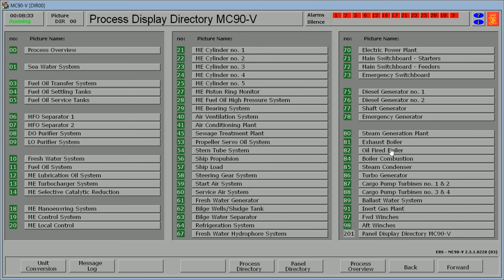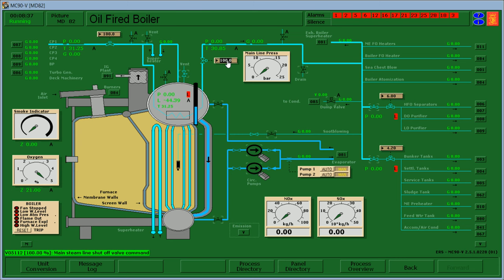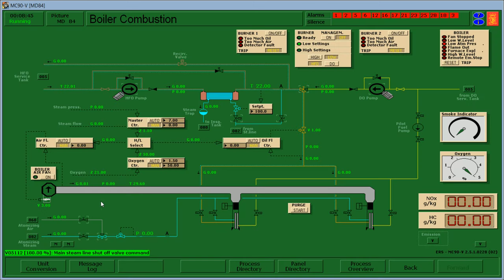Then proceed to the steam generation plant, oil fired boiler. We open the vent, close the steam line, then for the boiler combustion, open the atomizing air shutoff valve and click the three-way valve. Open the boiler air fan. Set the airflow to 100. Set the master control to 10. Oxygen control to 10. Oil flow to 10. Set diesel, open diesel, then start the purging.